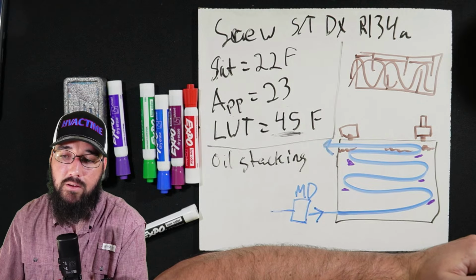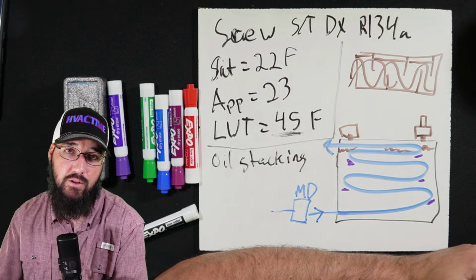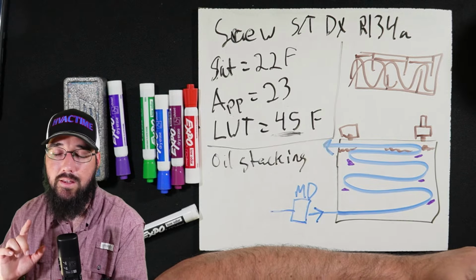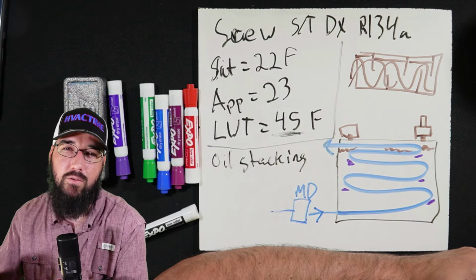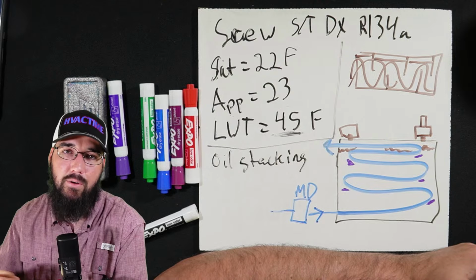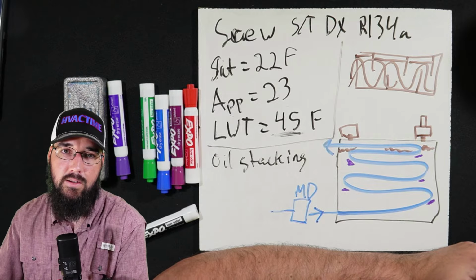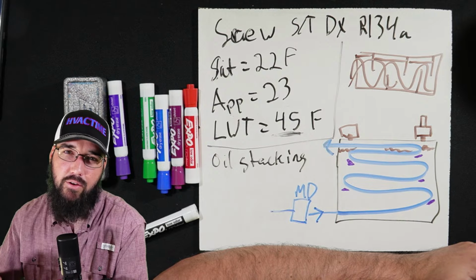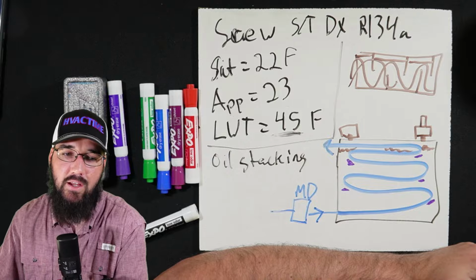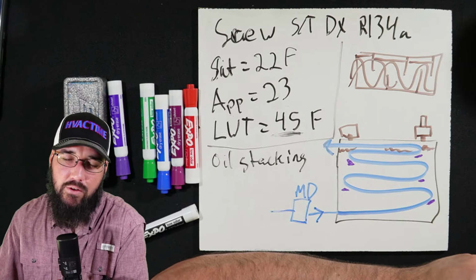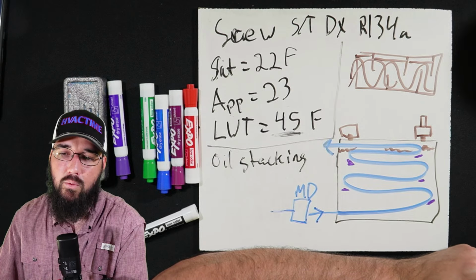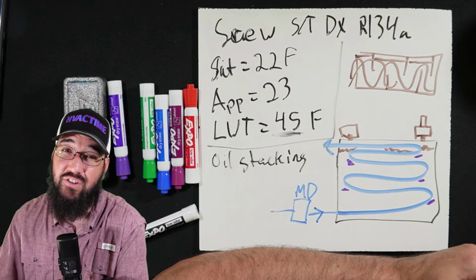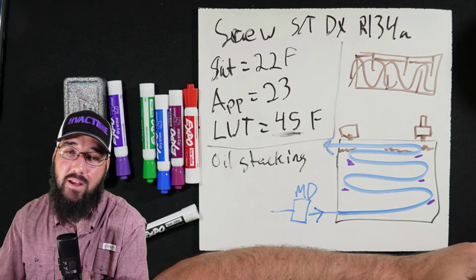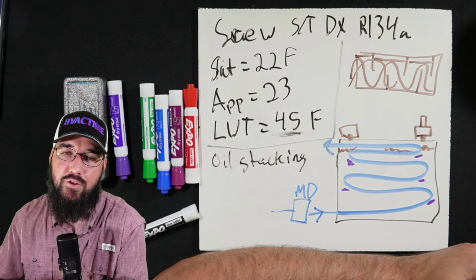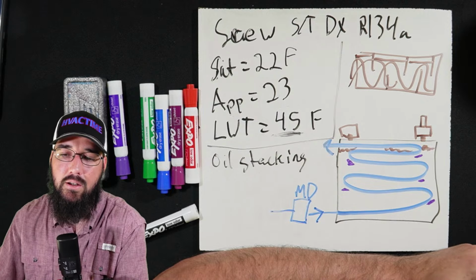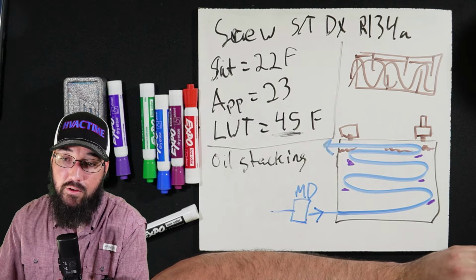while you can make an argument that we would expect to see this across multiple chillers if it was something like a low load issue, that is true, but it also gets into just the nuance of sometimes weird things happen, and it comes back to how each chiller ties into the load and the water flow. Just because there's 5 others doesn't necessarily mean they're all for sure going to have the same symptoms, and it comes back to where that chiller is on the header, which affects how the water goes through it. And it could be affecting that chiller just slightly more, right? It's possible that the other chillers have just enough turbulence and GPM through them where they're not having that stacking issue, where this particular one is.